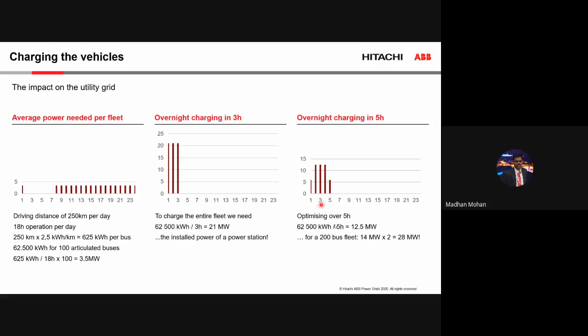Now we are again adding more. This is only terminal charging, this one with a flash charger. Now you are further reducing the total power demand to only 3.4 megawatt, and also it is distributed. So it is very clearly given to the grid operator that my maximum peak demand from the load will not exceed 3.5 megawatt, so that the infrastructure can be planned accordingly. But in the previous case, you can see the infrastructure requirement was 21 megawatt and 12 point something megawatt.